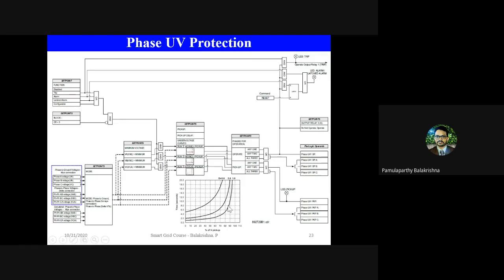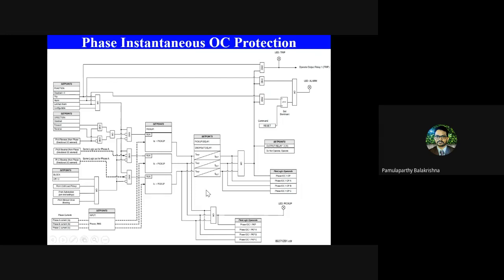So basically it's a curve mechanism, so that enough time is given for the other load control mechanisms to take action and the voltage may come back to a normal level. If the voltage is still at an undervoltage level and doesn't come back, then it will take a control action or the pickup action, like in the earlier case. Okay, so this is another way of configuring the timer. Then you have instantaneous overcurrent.